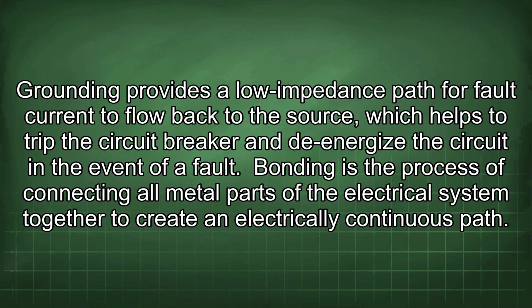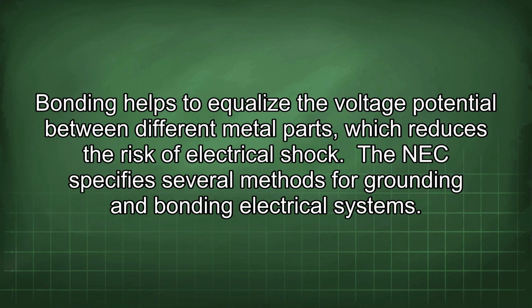Grounding provides a low impedance path for fault current to flow back to the source, which helps to trip the circuit breaker and de-energize the circuit in the event of a fault. Bonding is the process of connecting all metal parts of the electrical system together to create an electrically continuous path. Bonding helps to equalize the voltage potential between different metal parts, which reduces the risk of electrical shock. The NEC specifies several methods for grounding and bonding electrical systems.